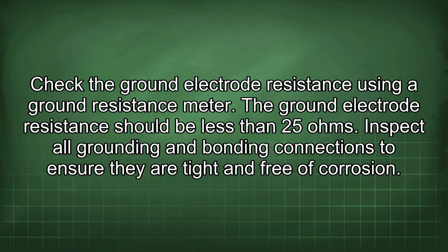Check the ground electrode resistance using a ground resistance meter. The ground electrode resistance should be less than 25 ohms. Inspect all grounding and bonding connections to ensure they are tight and free of corrosion.